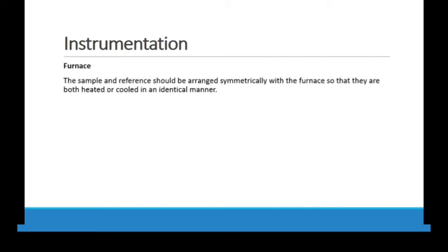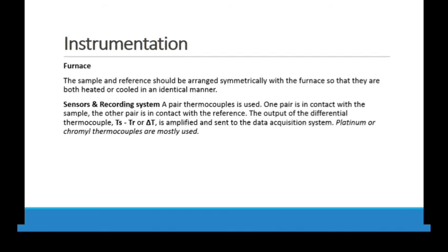The sample and reference should be arranged symmetrically within the furnace so that they are both heated and cooled in an identical manner. A pair of thermocouples is used — one pair in contact with the sample and the other in contact with the reference. The output of the differential thermocouple, which is TS minus TR (temperature of sample minus temperature of reference, or delta T), is amplified and sent to the data acquisition center. Platinum or chromium thermocouples are mostly used.